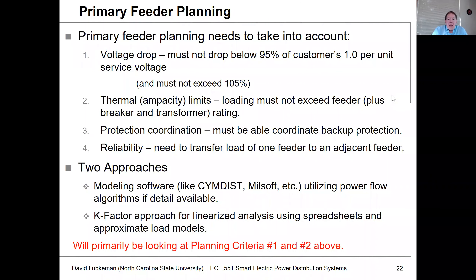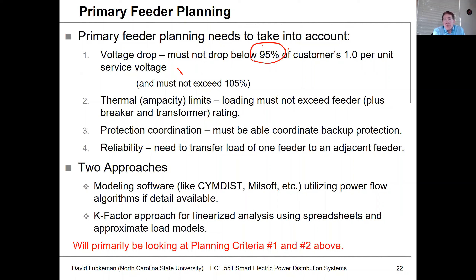In primary feeder planning, there are a number of different things you need to be looking at. You're going to be looking at voltage drop, and what's important is that the voltage doesn't drop below 95% of nominal. There's also a requirement that it doesn't exceed 105%, so you just can't boost voltage arbitrarily. We'll spend a lot of time on voltage drop this semester.